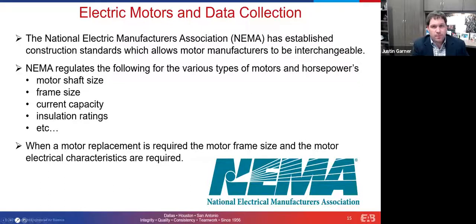And so some of the most important things, we'll talk more about this in detail on the next slide, are motor shaft sizing, frame sizing, and the electrical characteristics of the motor. If you've ever had to replace a motor and you call a supply house, they're going to need to know what the horsepower of the motor is, what the frame size of the motor is, what voltage you need, and things of that nature, as well as the speed. All those things tie into these NEMA designations and standardizing, to some extent, the motors out there in the industry.